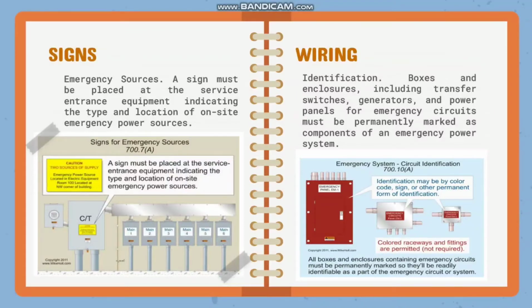For identification of wiring, boxes, and enclosures including transfer switches, generators, and power panels for emergency circuits must be permanently marked as components of an emergency power system. Identification may be by color code, sign, or other permanent form of identification. Colored raceways and fittings are permitted but not required. All boxes and enclosures containing emergency circuits must be permanently marked so they'll be readily identifiable as a part of the emergency circuit or system. So dito, color code and sign yung means of identification na these boxes and enclosures contain emergency circuits.